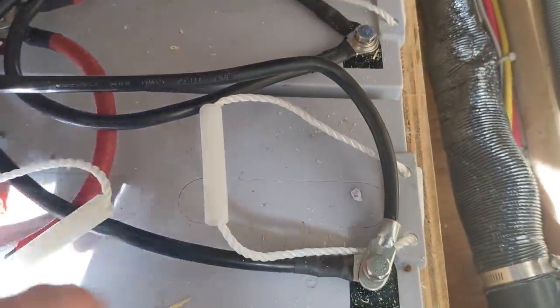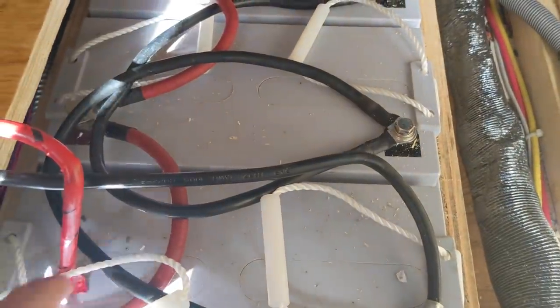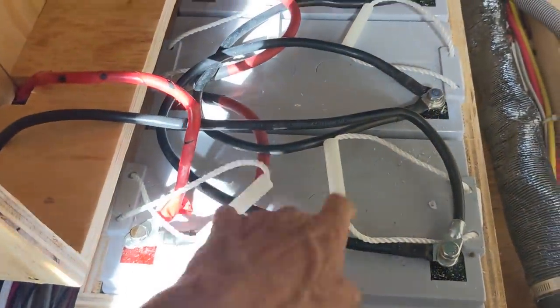And these batteries are connected just off one end. There's no opportunity for balance. Ideally, you go positive here and negative over there, or with a bank this big, maybe in the middle, like here and there. But just drawing off one end, especially with the fairly high resistance.